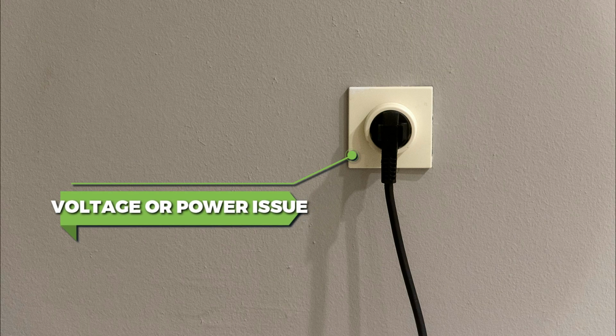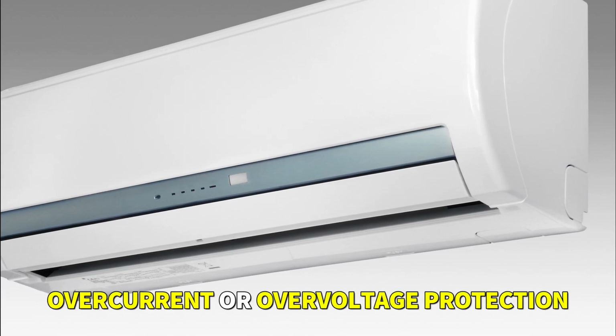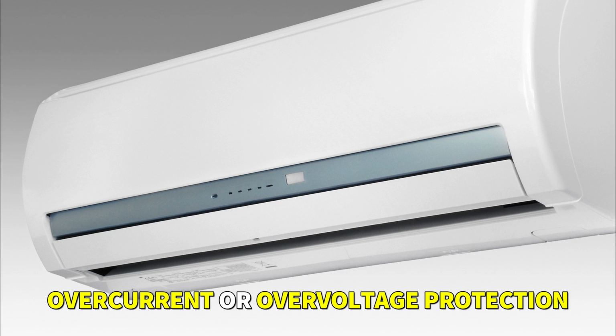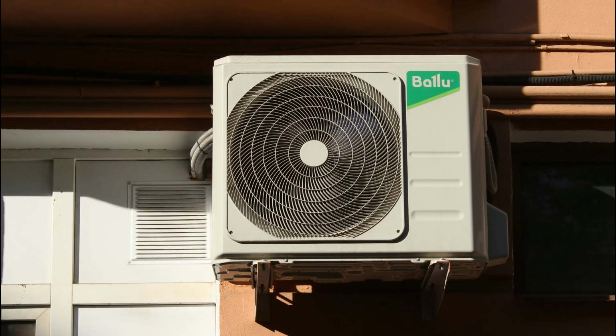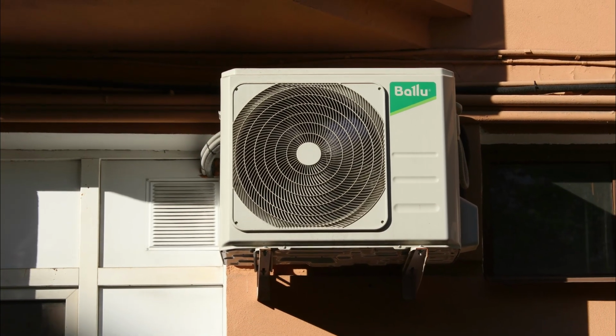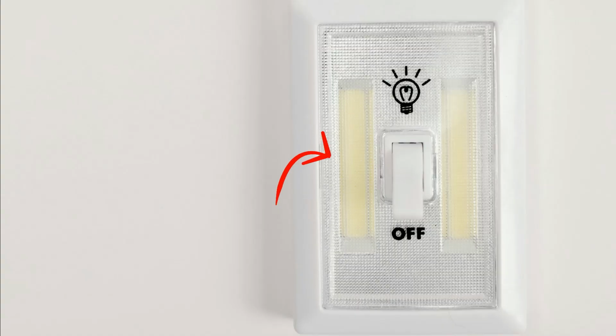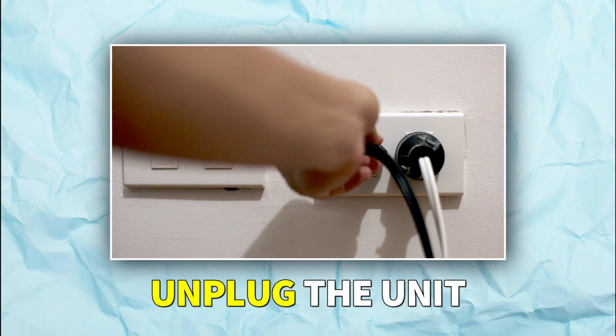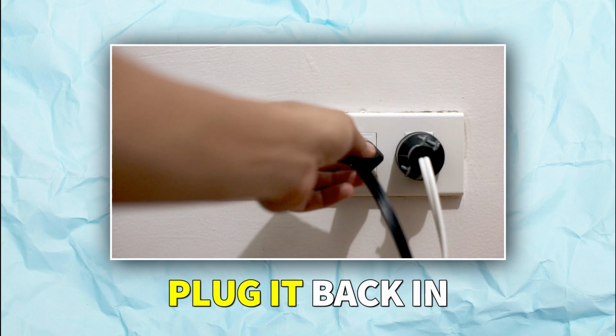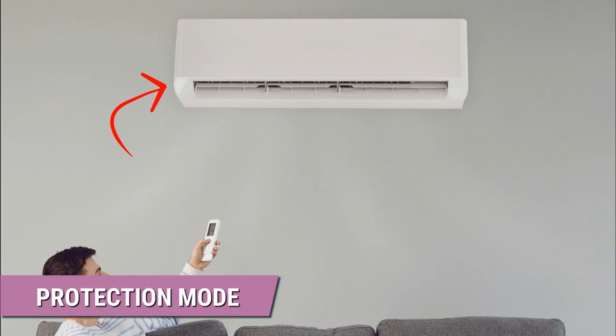If your AC won't turn on and all it does is show an E5 error, you're likely dealing with a voltage or power issue. On Gree units, E5 usually means overcurrent or overvoltage protection has kicked in. Your unit is shutting down to prevent damage from operating under abnormal conditions. So go to the power source and turn it off. Also, unplug the unit from the power source, wait for about 10 minutes, then plug it back in and restart. Most of the time, that clears the protection mode.